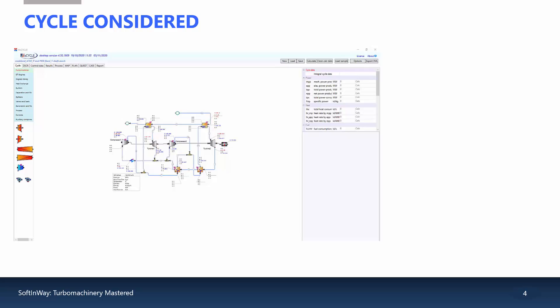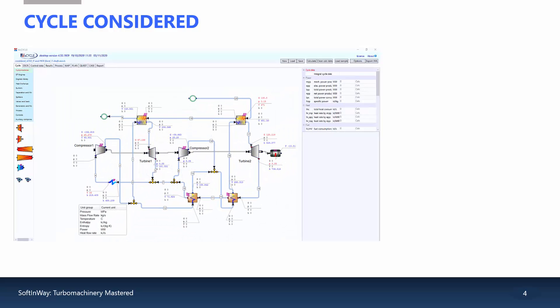Here we have a 15.5 megawatt bottoming power generation unit with a GE LM6000PH DLE gas turbine as the heat source to illustrate the concept. The PGU is a composite supercritical CO2 cycle with a high heat recovery rate to increase gas turbine unit efficiency and decrease the environmental footprint.